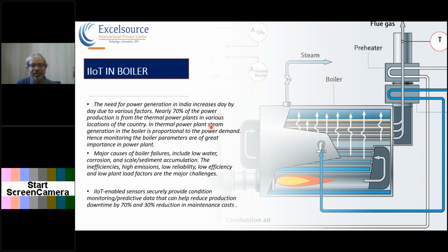That has to be taken into consideration, and then we need to take action when the heat recovery starts deteriorating. We need to go for CIP cleaning, or replacement of the heat exchangers in the longer run. Let's say about 25 to 30 years, we need to replace those heat exchangers. So IoT basically helps us optimize production to always be more than 70%, and a 30% reduction in maintenance cost is definitely achieved by implementation of IoT.